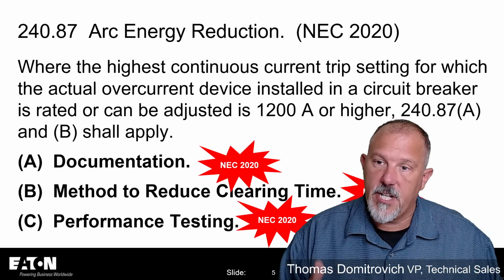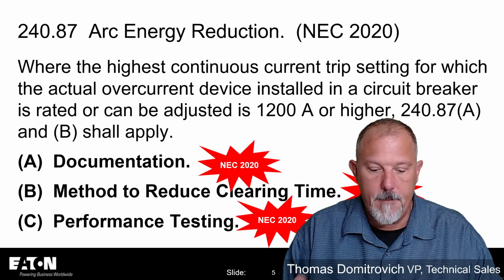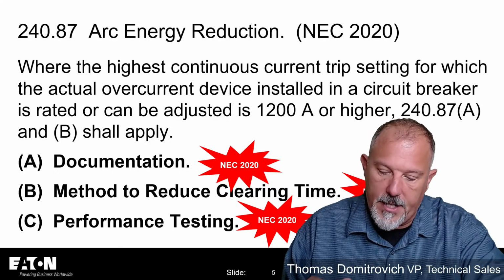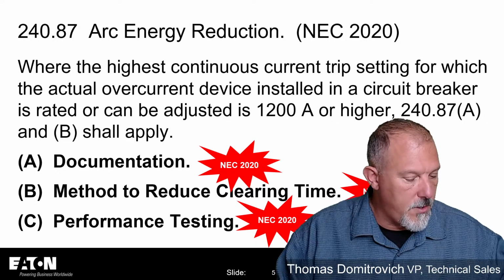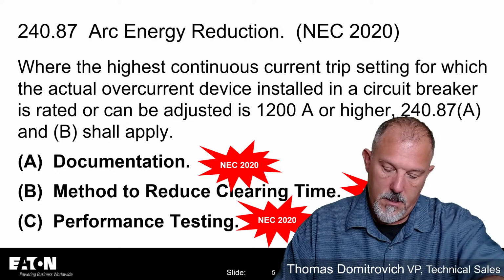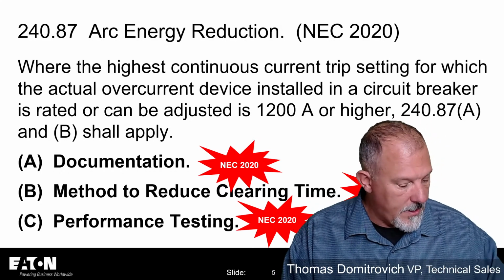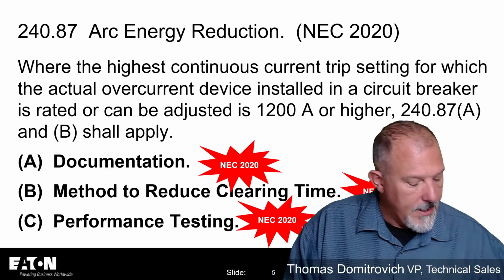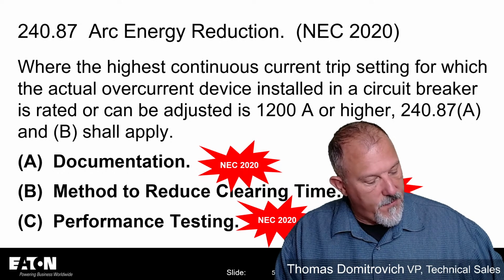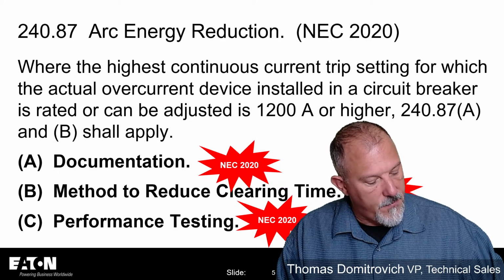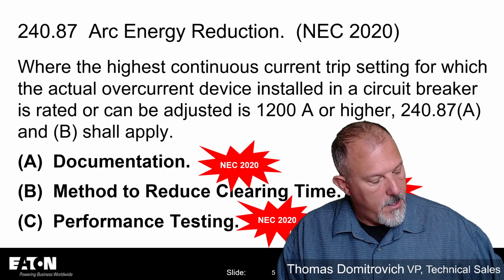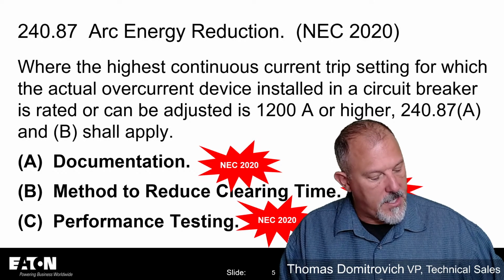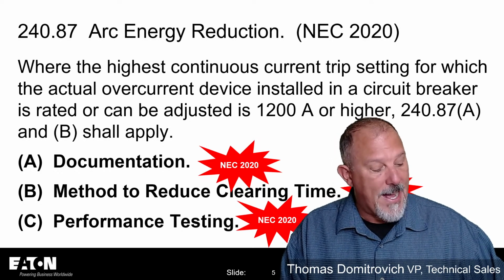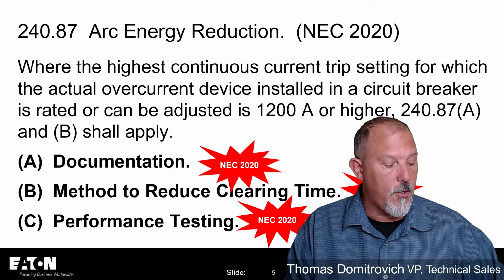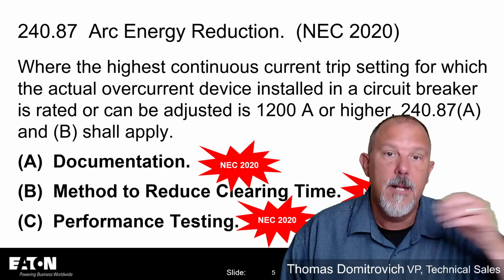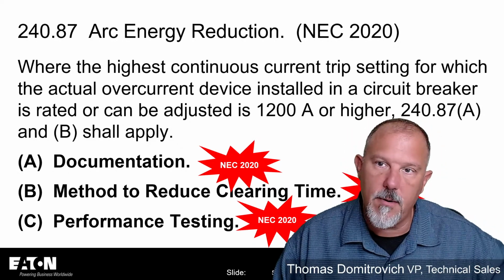Very similar to ground fault protection of equipment. Okay, so GFPE is the 1000 amps. If you go to 230.95, I believe it is, ground fault protection of equipment says: more than 150 volts to ground, but not exceeding 1000 volts phase to phase, for each service disconnect rated 1000 amps or more. The rating of the service disconnect shall be considered to be the rating of the largest fuse that can be installed or the highest continuous current trip setting for which the actual overcurrent device installed in a circuit breaker is rated or can be adjusted. So that's where we got that language from, 230.95 for ground fault protection of equipment.